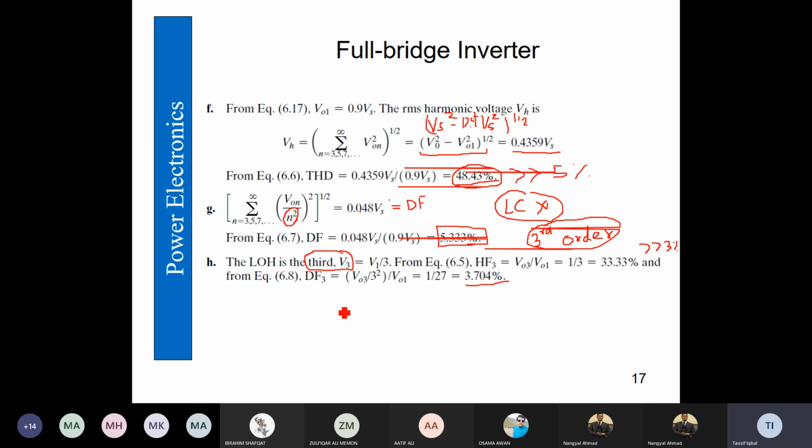ठीक है, यानी कि हम ऐसी टेक्निक यूज करते हैं PWM जनरेशन के लिए, so that we don't have harmonics in the output voltage. ठीक है, और उन टेक्निक में से फिर वो आ जाती है साइन PWM के साइनोसॉइडल रेफरेंस को देखते हुए हम PWM जनरेट करें, so that our output voltage is very close to sinusoidal 50 Hz. ठीक है, और जो हार्मोनिक कंटेंट है that is reduced as desired. सो साइन PWM अगर हम प्रॉपरली जनरेट करें विद इवन डेड टाइम्स एंड सो ऑन, सेफ्टी को भी सामने रखते हुए, then the total harmonic distortion is even less than 5% and sometimes it is around 1.5%, which means the output voltage is very close to sinusoidal voltage.